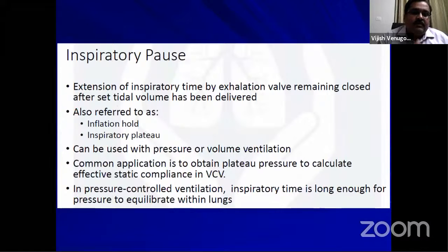expiration. During this phase, you can add something called an inspiratory pause. This is at the end of the inspiration during the cycling phase, where you can give an inspiratory pause. This is an extension of the inspiratory time by the exhalation valve remaining closed after a set tidal volume has been delivered.